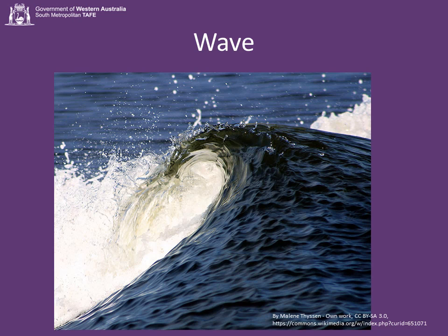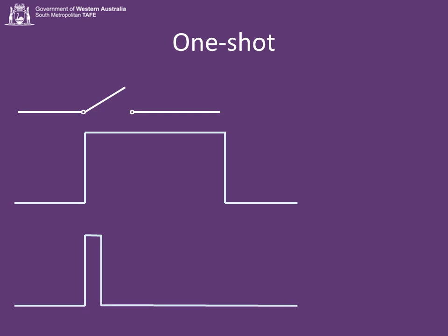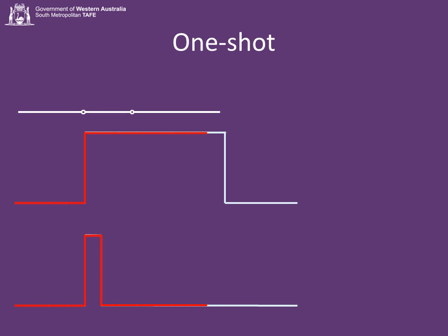The event triggers an off, on, off, which is a square wave traveling in time. So it has a leading edge and a trailing edge. If we only want the event to trigger once on a leading edge, we use the software function called a one-shot. It comes on for one execution. It literally, one shot is fired each time the trigger is pulled.